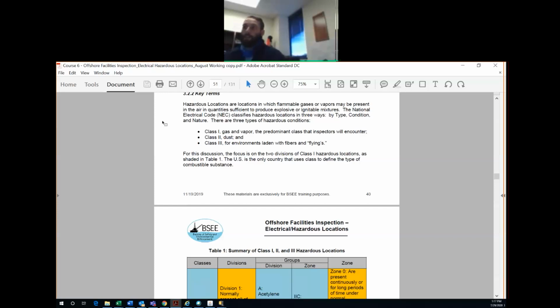And the reason why is because class 1 is the most conservative, right? So if you're talking about class 1 for a flammable or ignitable atmosphere, you're talking about the most conservative way to classify a platform. And we have gases and vapors offshore. So we're already classifying the platform in the most conservative way. Yes, we might have situations on the platform where there are dust or fibers, but if we classify it to dust and fibers, it would be less conservative than if we were to classify the platform to gas and vapor. So that's why you really only hear about class 1 in the offshore environment. Everything is class 1.